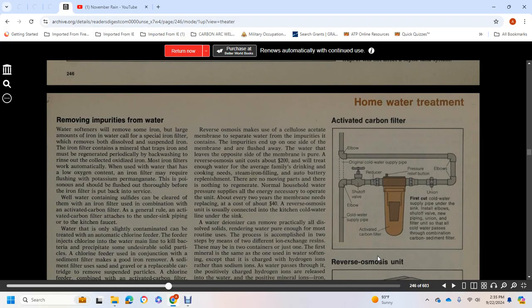Removing impurities from water. Water softening will remove some of the iron. Large amounts of iron call for a special iron filter, which removes both dissolved and suspended iron. The filter contains a mineral that traps the iron and must be regenerated periodically with a backwash to rinse out the collected oxidized iron. Most iron filters work automatically when used to wash water. When used with water that has low oxygen content, the iron filter may require flushing with potassium permanganate, which is poisonous and should be flushed out thoroughly before the iron filter is put back in service.